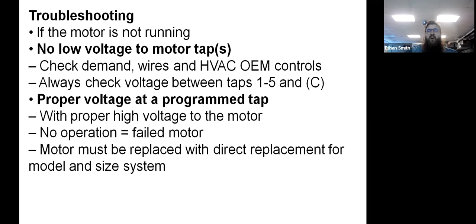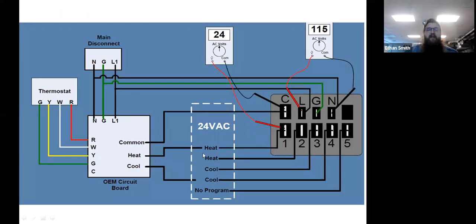That's it. That's all the diagnostic you have with these things. Check for high voltage and low voltage. If you've got both of those, motor doesn't run, motor is dead. Look for water. That's what kills most of these things. Okay. So you can do that with your meter. Simply get on your 120 volt side and the low voltage side.